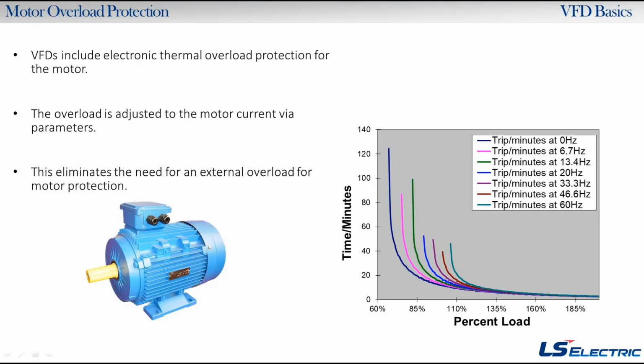And here's just the time current curve. They're showing that if you're at 60% load, you're going to be able to run pretty much forever. But if you start overloading over 100%, we're going to severely start limiting your time. And then same goes for speed too. If you're running at a very low speed and a high amperage, we're going to trip you out pretty quick because we're going to assume that the motor isn't sufficiently cooling itself the same as it would at a higher speed. So it depends on speed, it depends on time, and it depends on your load or current. But this is all programmed in with just 1 or 2 parameters, so very easy to set up.